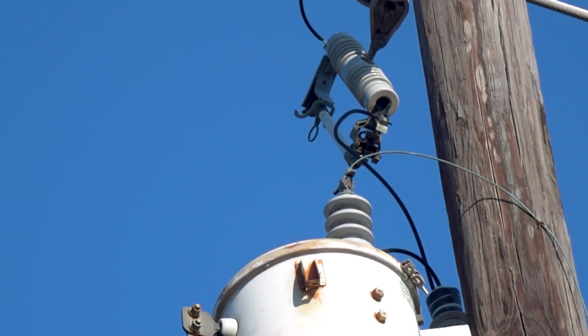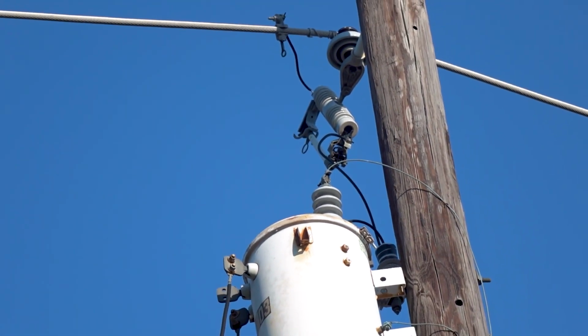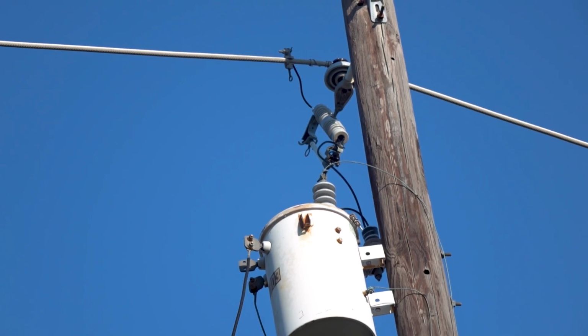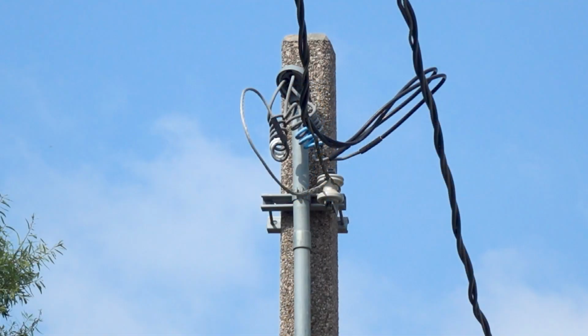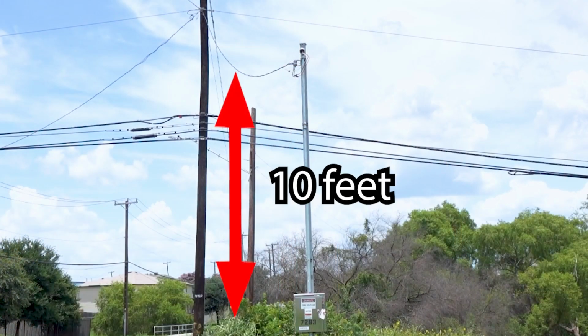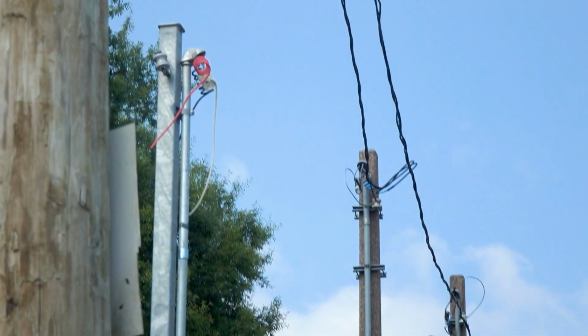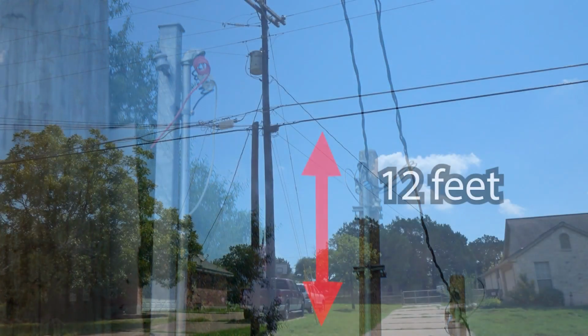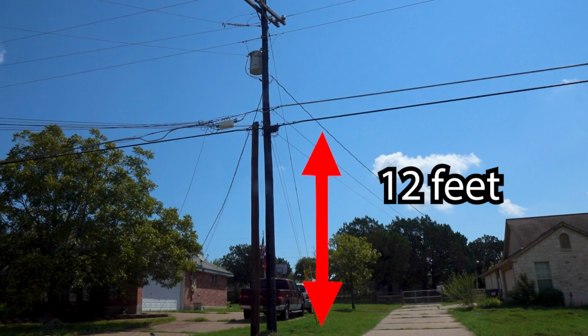The conductors that connect from the utility transformer near the top of the utility pole to the conductors coming out of the weatherhead are called service drop conductors. The National Electrical Code, NEC, specifies that the lowest point these conductors can be above finished grade is 10 feet. Where the space under these overhead conductors is wide enough to allow vehicular traffic, such as a residential driveway that is not subject to truck traffic, the clearance must be at least 12 feet above finished grade.